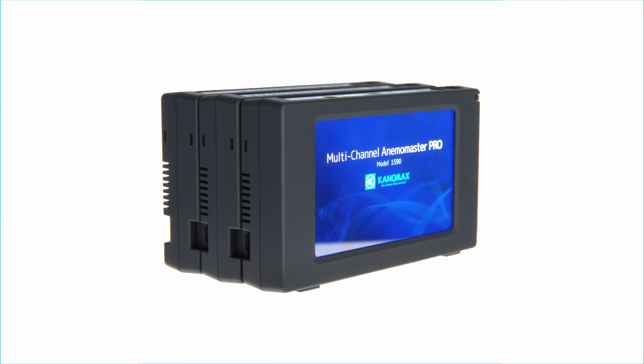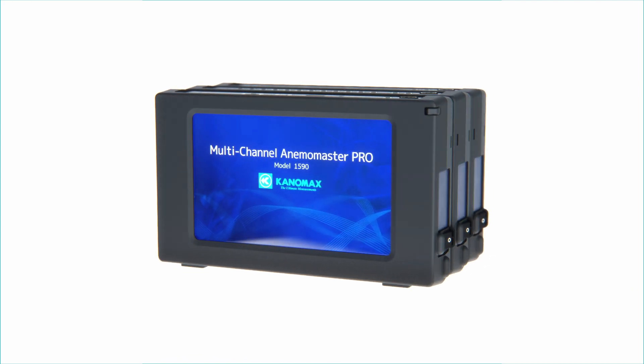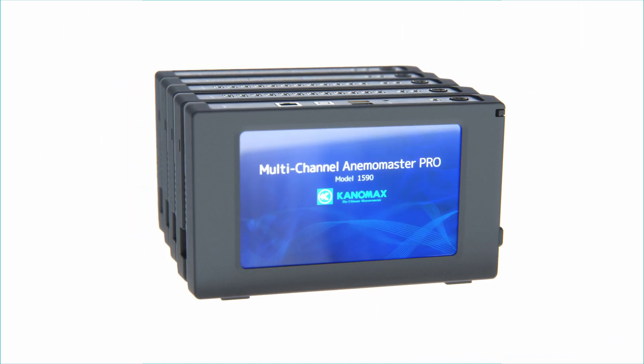For overviewing the parts and functions of the Kanomax multi-channel AnemoMaster, we'll be using the model 1590 since it operates similarly to the 1580. The major difference between the two is the 1590's dedicated interface unit and its ability to scale up and work with a greater number of hub and analog units, increasing the number of probe and analog channels available.